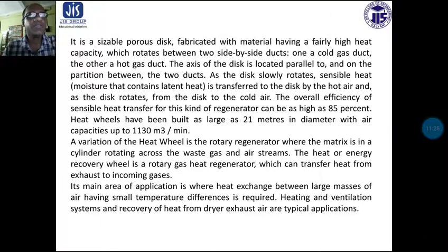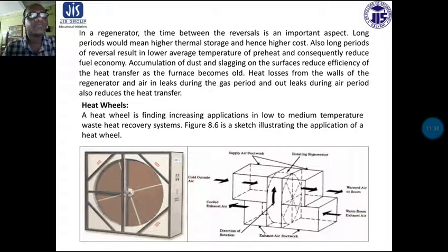It is a sizable porous disc fabricated with material having a fairly high heat capacity, which rotates between two side-by-side ducts. One is a cold gas duct, the other a hot gas duct. The axis of the disc is located parallel to and on the partition between the two ducts.